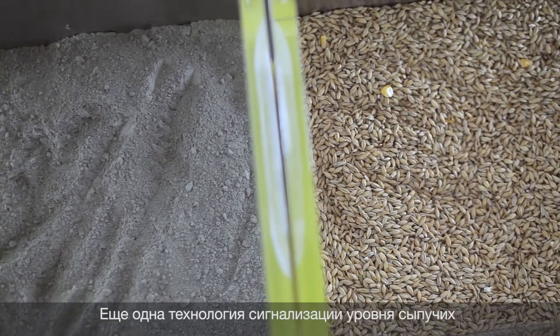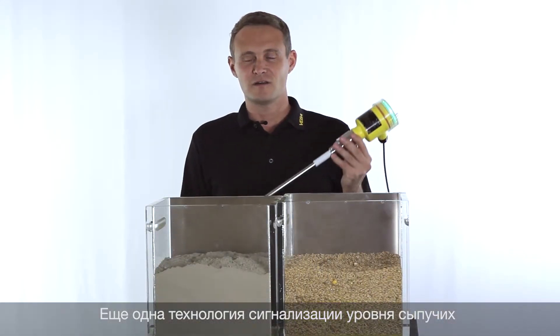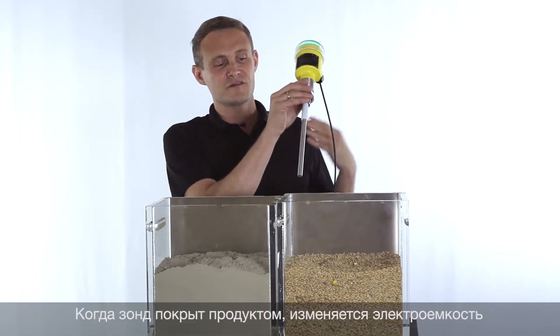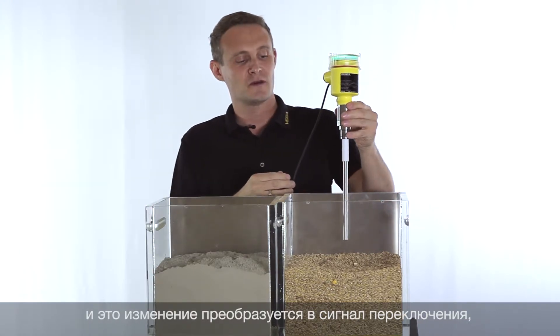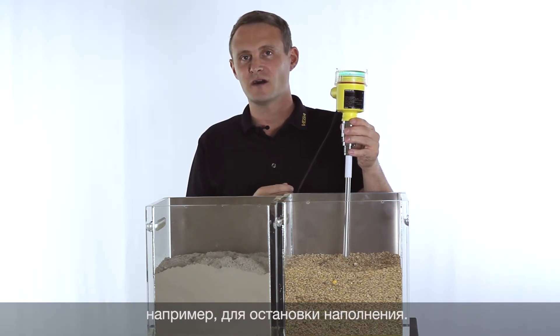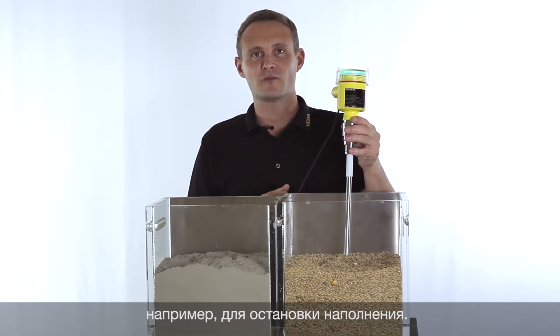Another possibility to detect the level of bulk solids is using a capacitance probe like the VEGACAP series 60. The probe is submerged, the capacitance changes, and this capacitance change is then analyzed and converted into a switching output.